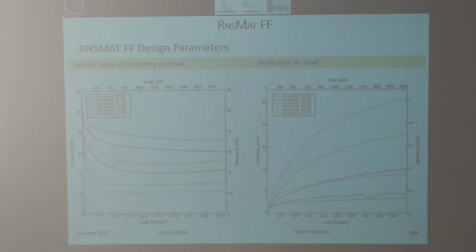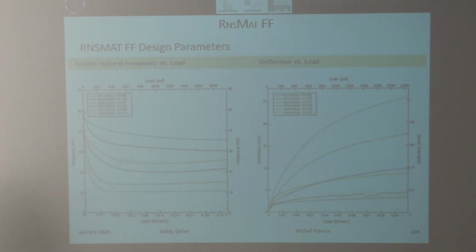If we look at performance, the performance of the load. Here, when we are increasing the load, PSI, you see that performance stabilizes after a certain time at frequency. Depending on the frequency, this is the natural frequency of the material, the frequency at which it will start to give vibration through. So when you increase the pressure, it stabilizes after some time. Depending on the type, you have 10, 15, 20, up to 25 hertz. That means very low frequency, which is a good thing, because normally noise is always above that level, above 80 hertz and above.